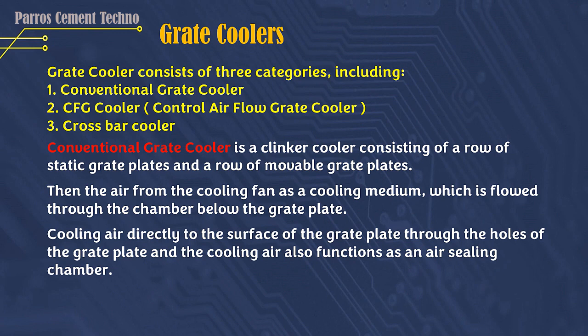Conventional grate cooler is a clinker cooler consisting of a row of static grate plates and a row of movable grate plates. The air from the cooling fan serves as a cooling medium, which is flowed through the space under the grate plate. Cooling air flows directly to the surface of the grate plate through the holes of the grate plate, and also functions as an air sealing chamber.